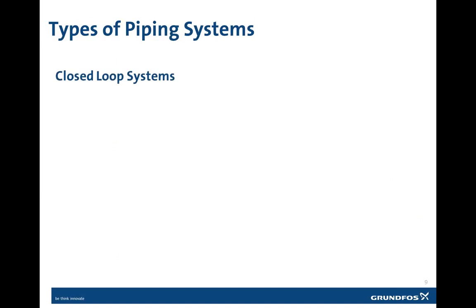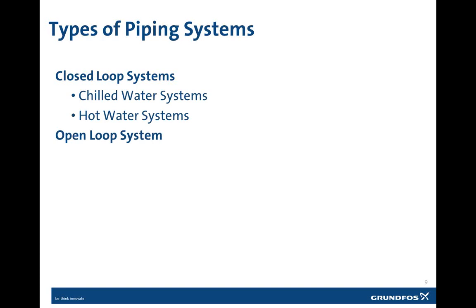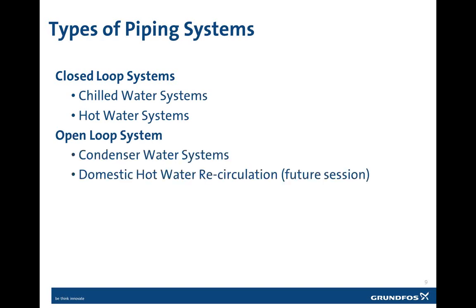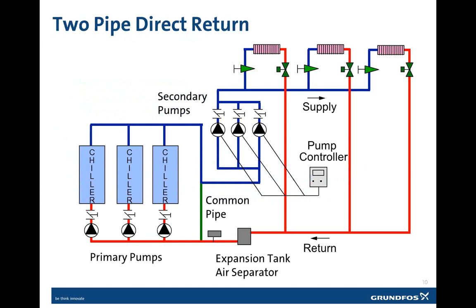There are two broad classifications for the piping systems, with some variations for these. The first is closed loop systems, which would include chilled water systems as well as hot water systems. The second is open loop systems, which could consist of condenser water systems and domestic hot water recirculation, and domestic pressure boosting could also be included in that. The diagram we're showing here is for a two-pipe direct return system.